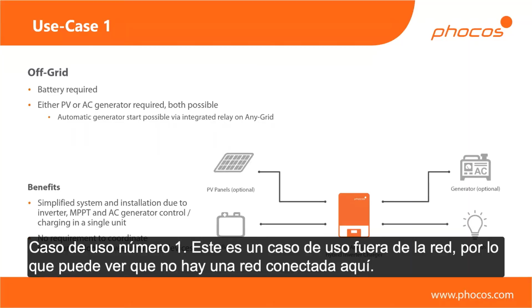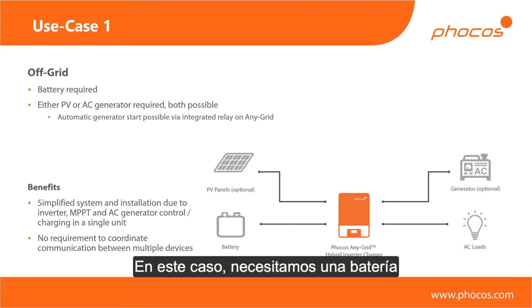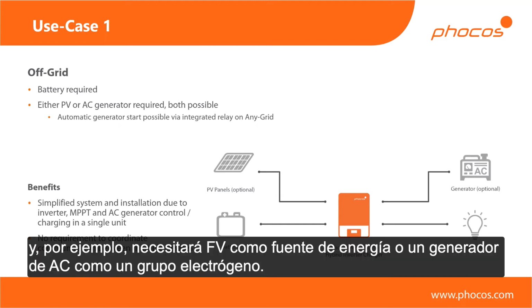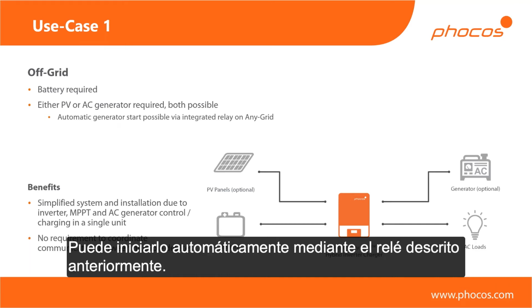Use case number 1: this is an off-grid use case, so there's no grid connected here. We do require a battery in this case, and you're going to need either PV as an energy source or an AC generator, like a genset, for example. You can start that automatically via the relay described earlier.